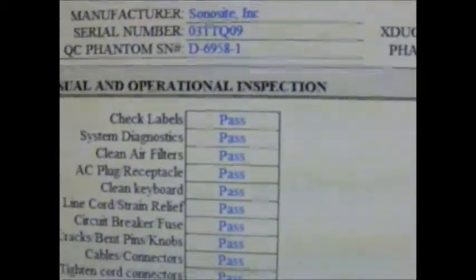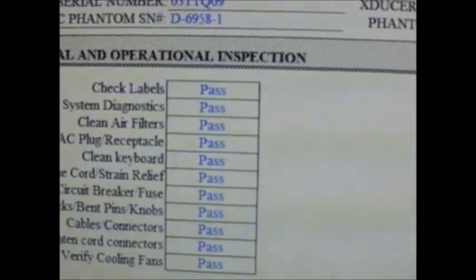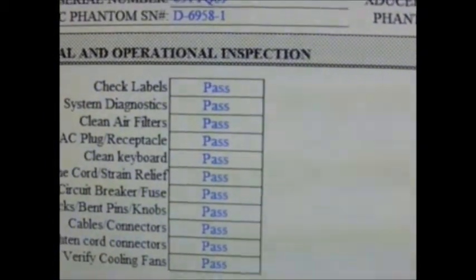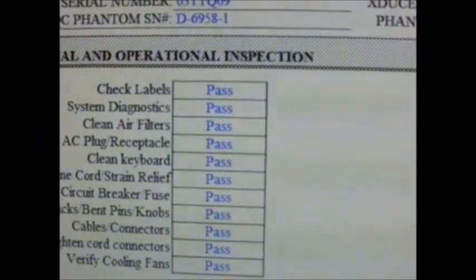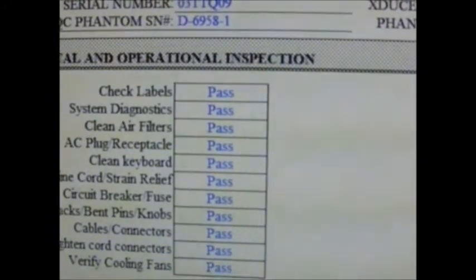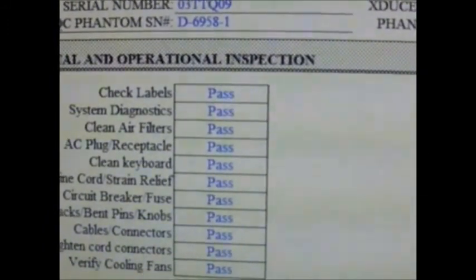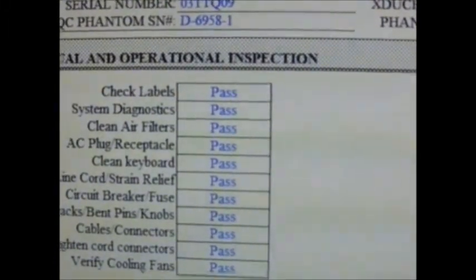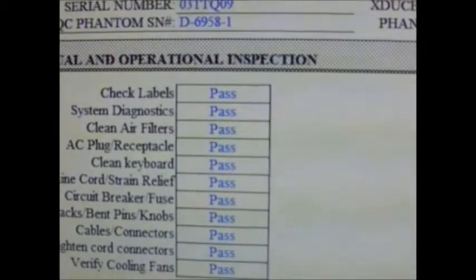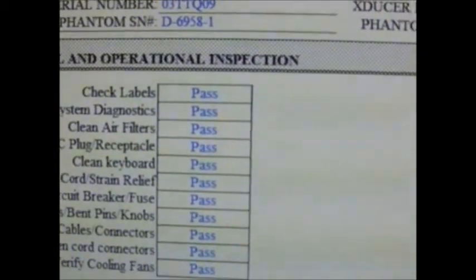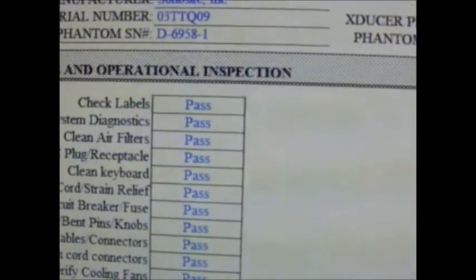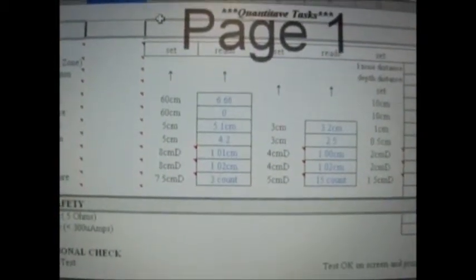Moving along, here are some visual and operational inspections. We will check the labels, check the system diagnostics, clean any filters or check the AC plug receptacles, the circuit breakers or fuses, any cracks or bent pins, check the fans. We will test the quality tests, beginning with uniformity.